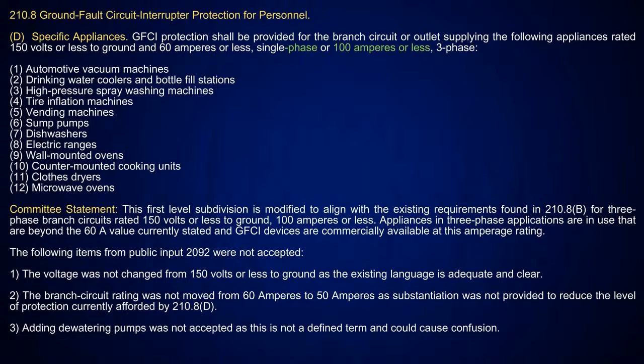I've stated over and over, if you wanted a specific appliance protected, when you look at the statement made in the 2023 NEC, they were very specific. They didn't care if it was cord and plug connected or hardwired - they wanted all these items to have GFCI protection. I stated a long time ago, if they really wanted GFCI protection, they should put an AC unit here. Yeah, I agree. I'm just pointing out a couple things I disagreed with in the 2023.